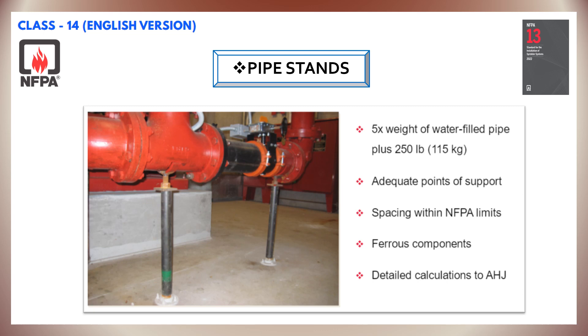The pipe stand base shall be secured by an approved method. Where pipe stands are utilized, they shall be approved by the authority having jurisdiction. Additionally, the pipe stands must be secured at their base to preserve the alignment of the system over its lifetime. And the distances between supports as per NFPA 13 need to be maintained.